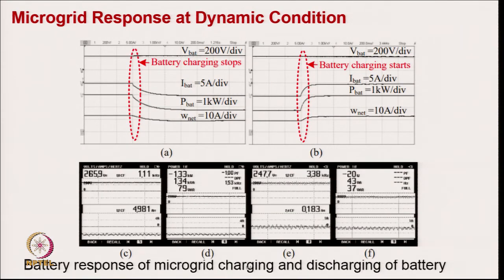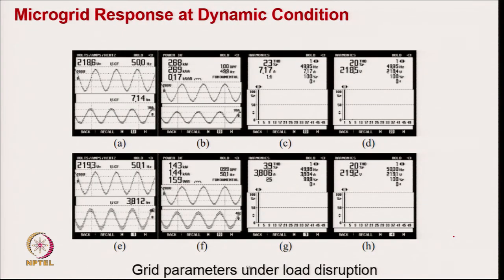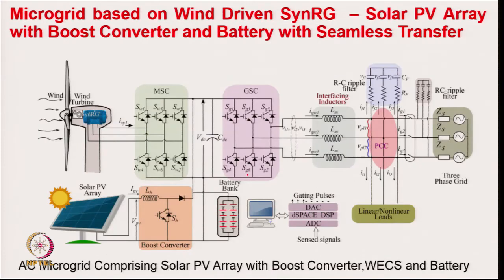The power flow into the battery is shown — battery charging stops when power generation decreases and then battery charging resumes. Power flow into the battery during load change dynamics is also demonstrated. The grid current THD is 2.3 percent with voltage THD of 2.0 percent. For different power generation levels — 2.69 kW and 1.43 kW — the grid current THD remains below 5 percent in all cases.